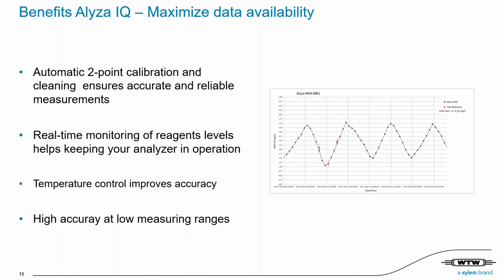So besides the easy maintenance and less reagent consumption, of course, accurate data are essential for measurement of effluents and surface water bodies. So as I keep mentioning, Alyza IQ Ammonium really provides highly accurate data. Thanks to automatic cleaning and an automatic two-point calibration, we ensure that the analyzer provides these accurate measurements with minimal human intervention. In addition, the mentioned real-time monitoring of reagent helps you to keep the analyzer in operation, so no longer unwanted gaps take place.